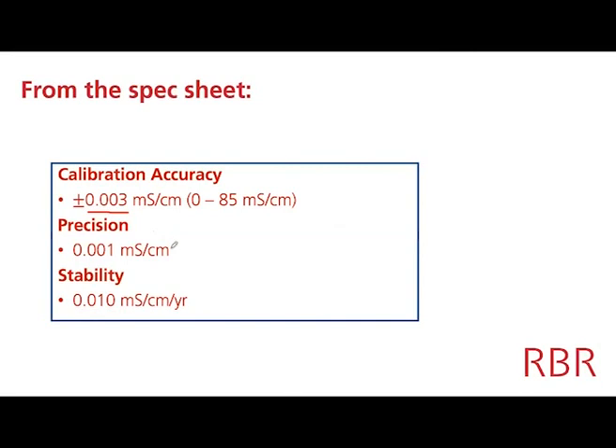The precision is about 0.001 millisiemens per centimeter. In fact, if you just put the instrument in still water, the RMS noise level is actually lower than this, but you know, this is what we put on our spec sheets. And we also, the calibration is stable to within 0.01 millisiemens per centimeter per year. Okay.